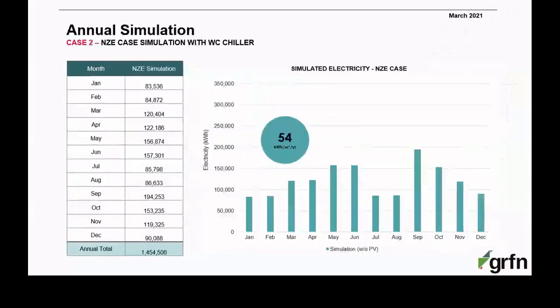This is the monthly simulation for the net zero energy case. There's a drastic improvement in the EUI. There's a drop from 118 to 54. That's almost a 60% reduction in energy consumption. And you can see the pattern. Obviously, we still have more consumption during the summer, but due to the high efficiency chiller plant, the increase in energy consumption between winter and summer is not that drastic.